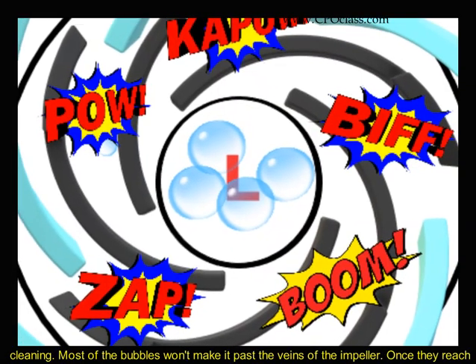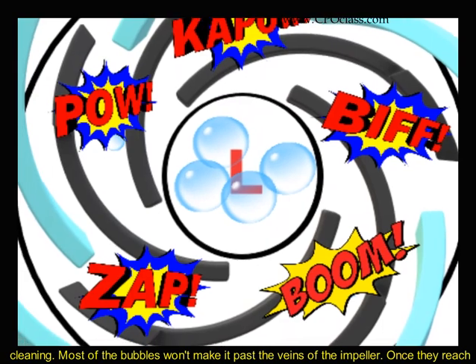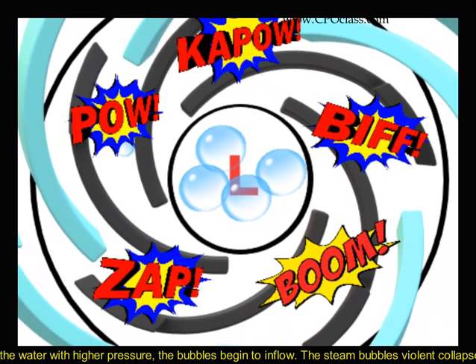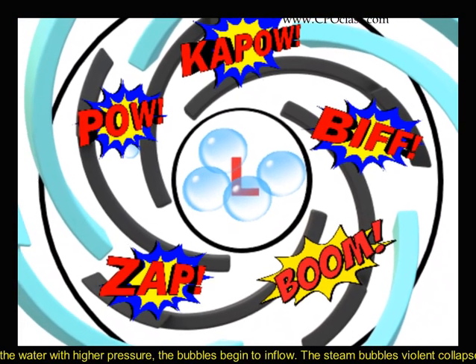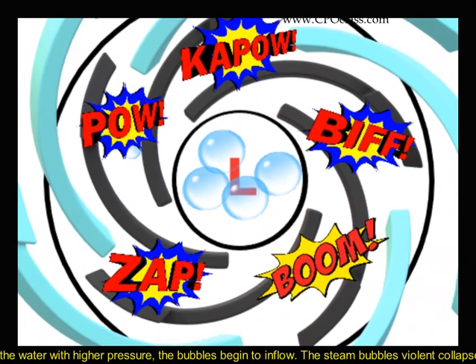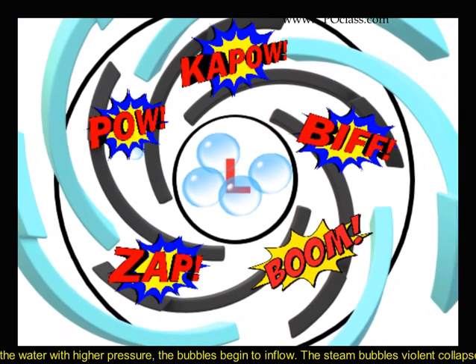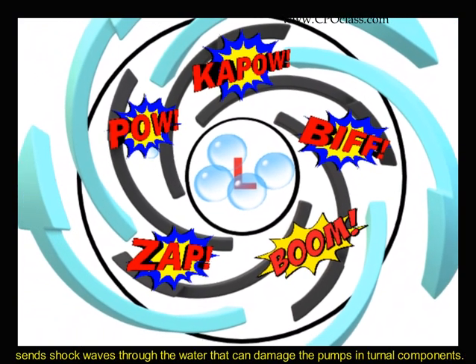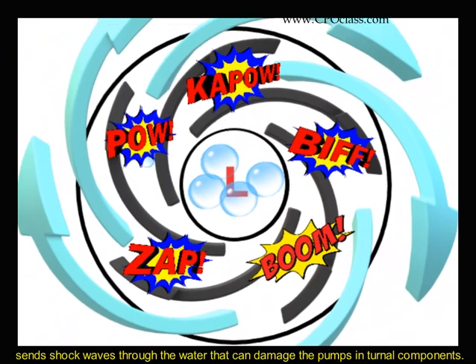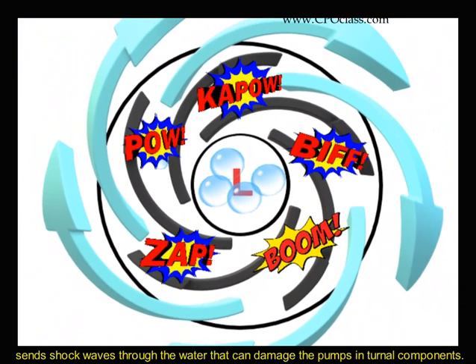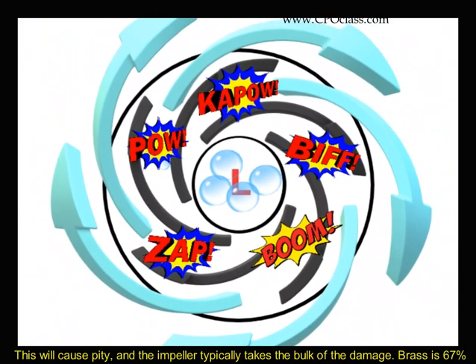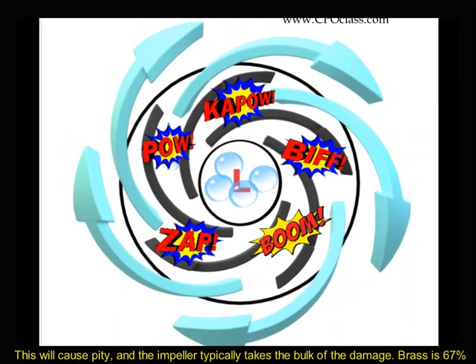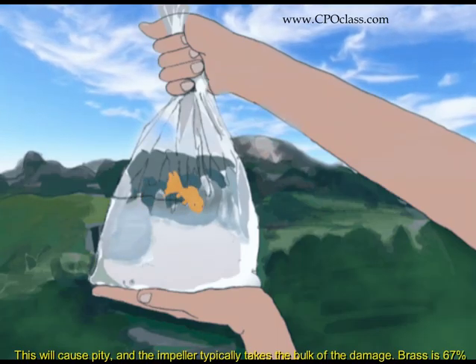Most of the bubbles won't make it past the veins of the impeller. Once they reach the water with higher pressure, the bubbles begin to implode. The steam bubble's violent collapse sends shockwaves through the water that can damage the pump's internal components. This will cause pitting, and the impeller typically takes the bulk of the damage.